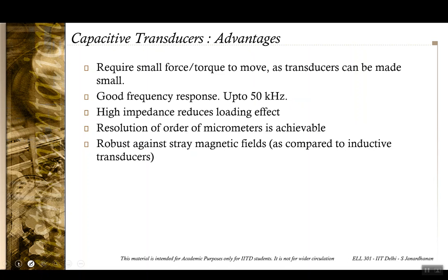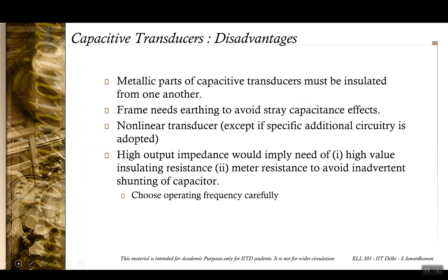However, all is not well. On the flip side, capacitive transducers are sensitive to stray electric fields, which would mean that the metallic parts of the capacitive transducers should be insulated from one another so that stray electric fields do not affect the capacitance, and in fact they should also be insulated from earth. Appropriate earthing should also be given to the circuit so they are not influenced by stray electric fields.